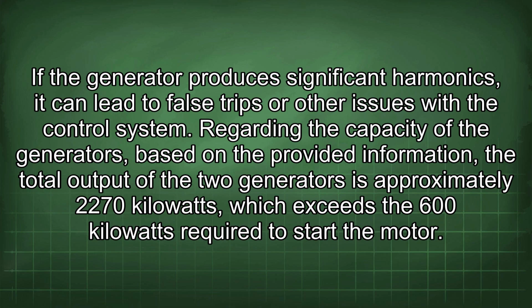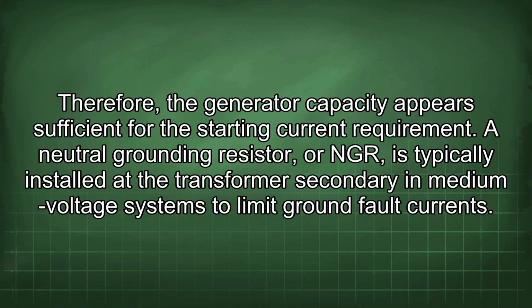Regarding the capacity of the generators, based on the provided information, the total output of the two generators is approximately 2270 kilowatts, which exceeds the 600 kilowatts required to start the motor. Therefore, the generator capacity appears sufficient for the starting current requirement.